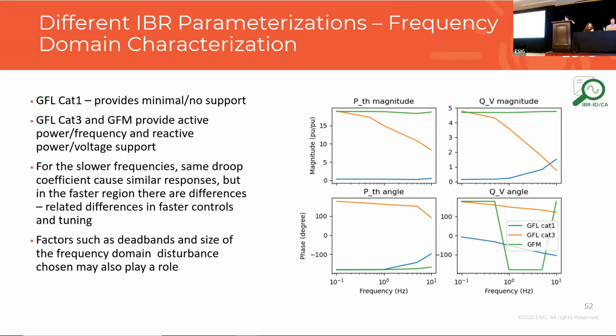What we see on the slower end of the frequency spectrum, on the extreme left-hand side of the first column, is that category 3 and the GFM resource are able to provide a good response, a good magnitude of response for a change in frequency. That's essentially because there's the capability for a governing-like response from the inverter, capability to provide something like fast frequency response and primary frequency response—some kind of frequency regulation capability is there.